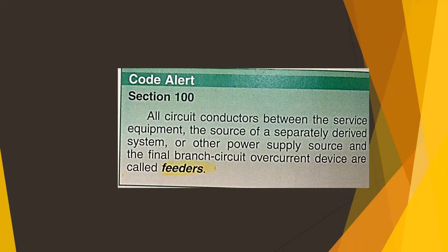Code alert, section 100. All circuit conductors between the service equipment, the source of a separately derived system or other power supply source, and the final branch circuit overcurrent device are called feeders.